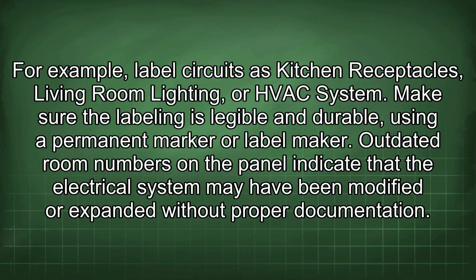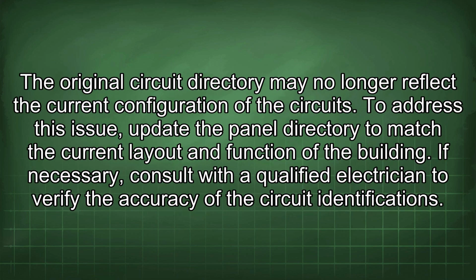Outdated room numbers on the panel indicate that the electrical system may have been modified or expanded without proper documentation. The original circuit directory may no longer reflect the current configuration of the circuits. To address this issue, update the panel directory to match the current layout and function of the building. If necessary, consult with a qualified electrician to verify the accuracy of the circuit identifications.